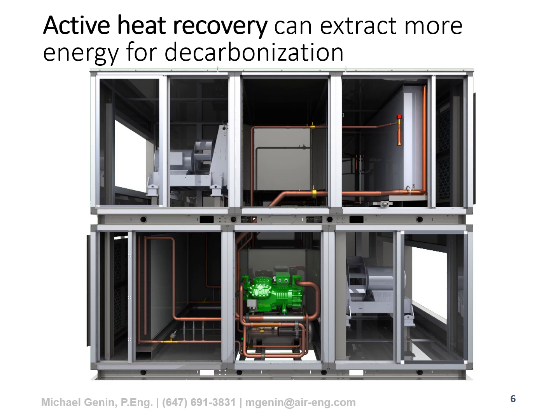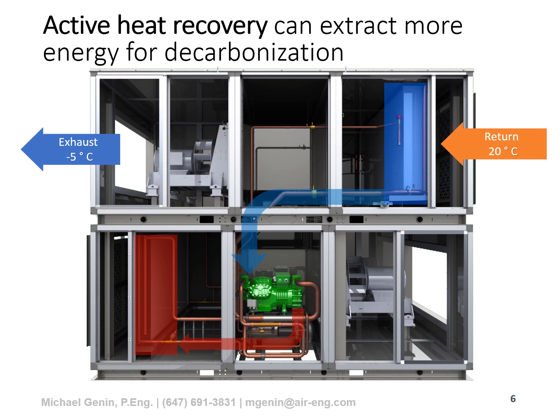Active heat recovery, on the other hand, can extract a little bit more heat energy from these air streams, and that proves to be useful for decarbonization. An active heat recovery, unlike a passive device, is going to use a compressor or refrigeration system to extract that additional heat energy. So what this looks like is return air coming over our cooling coil or evaporator coil in this case, and our compressor is going to suck out that heat energy and dump it into the condenser or heating coil. That return air, or air from the building, which is waste air, is cooled substantially more than it would be in a passive heat recovery device. Therefore, we have more heat available. So we can bring in our fresh air at -20, for example, and now we're able to heat that fresh air all the way up to 20 degrees or room neutral without any top-up heat energy.